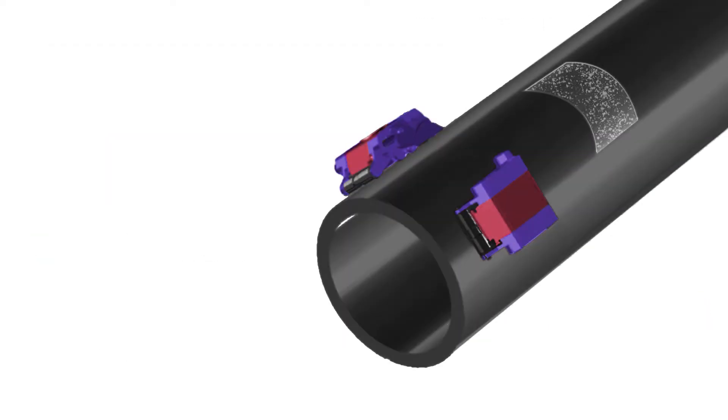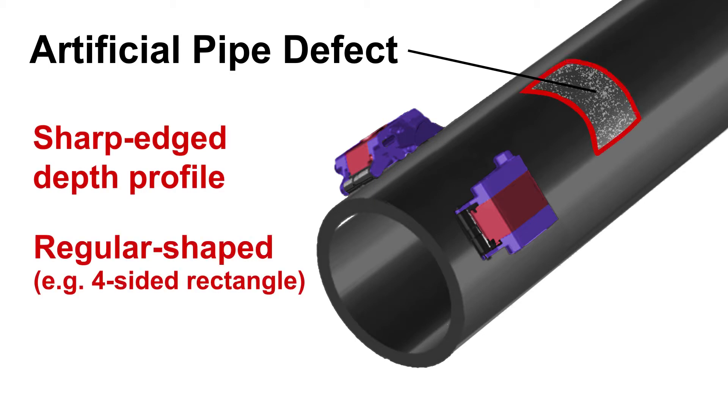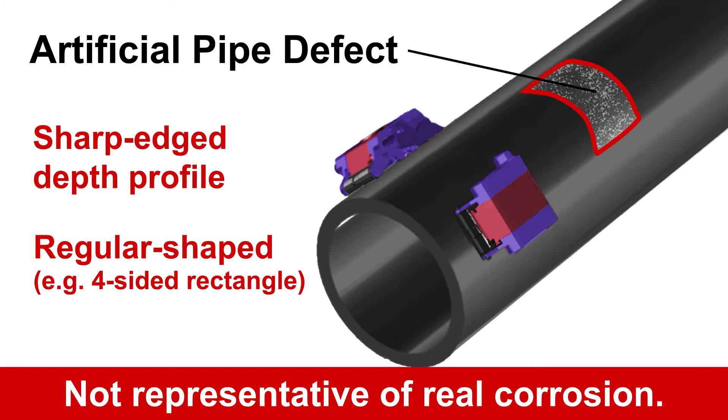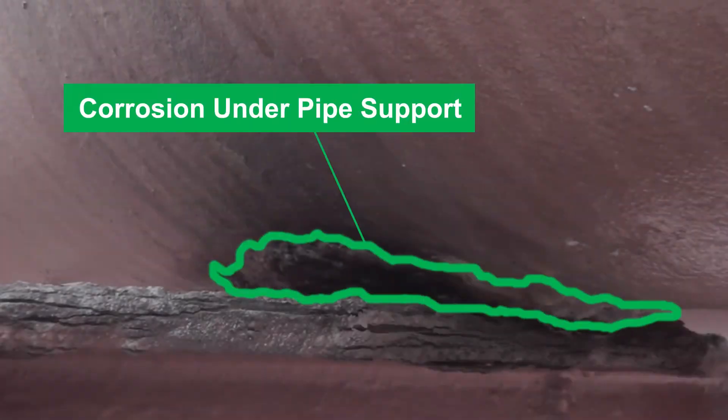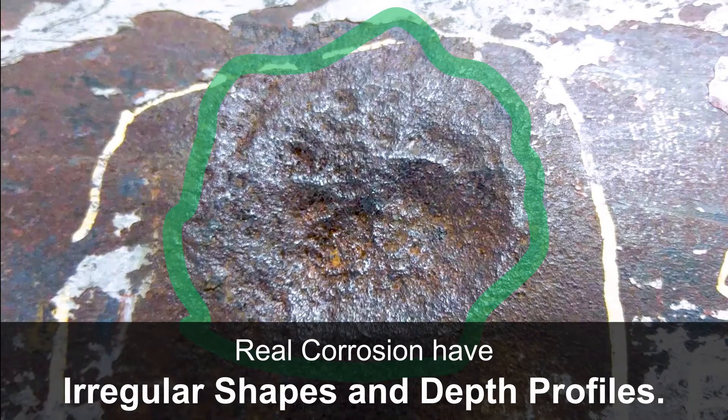Most amplitude-based products would be able to detect artificial pipe defects with sharp edges and regular shapes. However, this type of defect does not represent real corrosion in the field. In practice, real corrosion defects generally have irregular shapes and depth profiles.